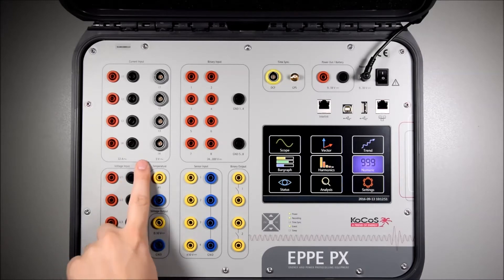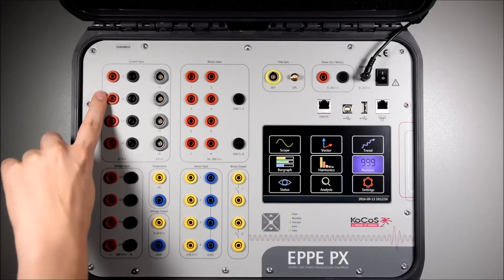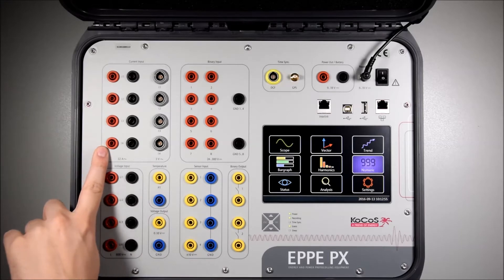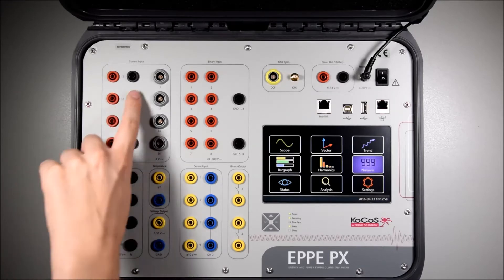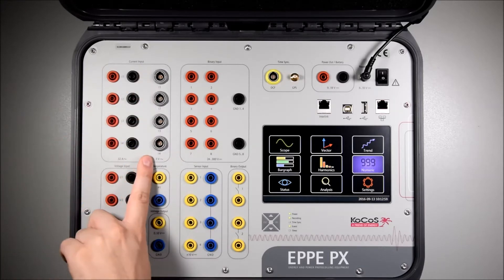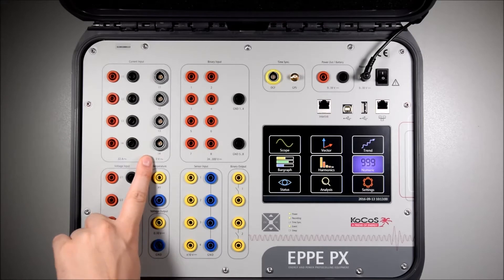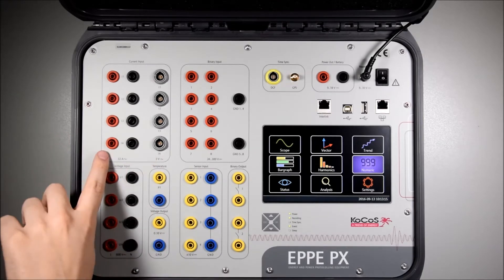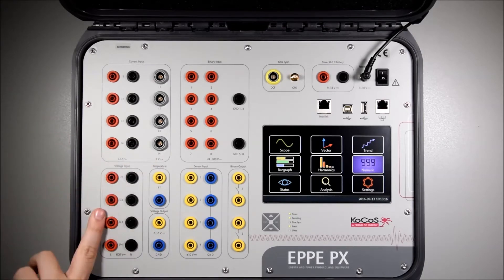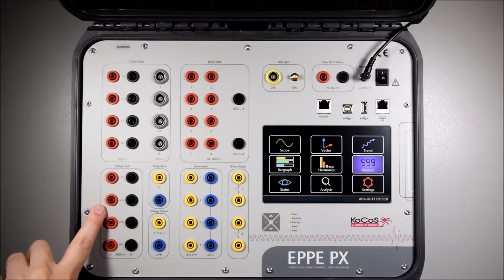Additionally, the PX has eight current inputs. Four inputs are for direct current measurement up to 32 amps and four inputs can be used for current sensors. Current and voltage inputs have a maximum sample rate of 200 kHz.